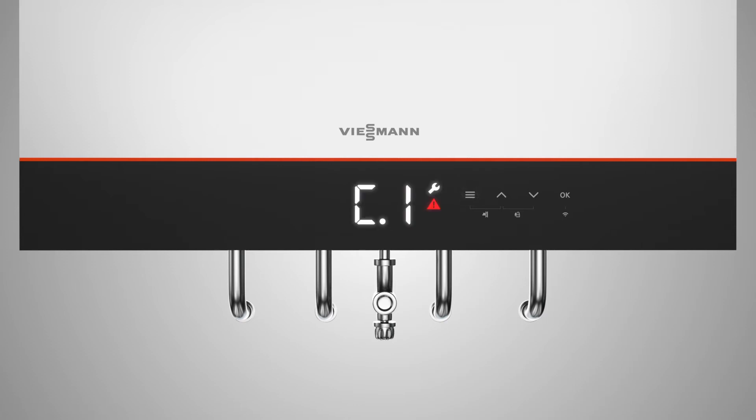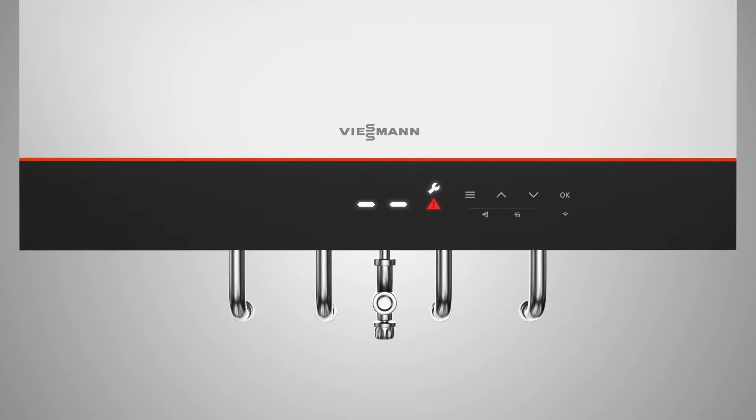Start the filling program. The display shows the pressure in bar. If the display shows two dashed lines, please check the pressure sensor located below the boiler. To end the filling process, press the menu key for approximately 4 seconds until the next step appears.